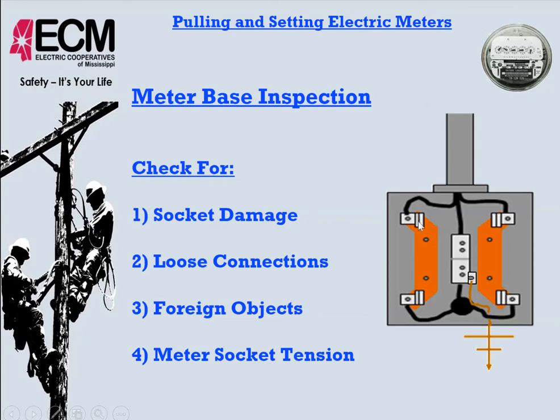Now either you or the electrician, whoever hooks up the line side and the load side, if it's a brand new meter base, these are fairly strong, but definitely trying to get the line side and the load side wire tight enough in the lugs to prevent loose connections and excessive heat and premature burnout. Sometimes these become over tightened. If that happens, maybe these are brittle. The plastic insulators that separate the hots from the nots, they're very easy to break. So one of the things that we can do to ensure that they don't is, one, we can support this with a pair of channel locks while we're tightening it. Also tighten it to the proper torque specifications for the meter base itself.